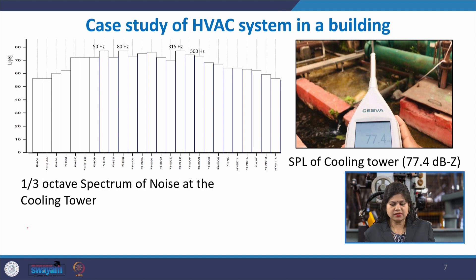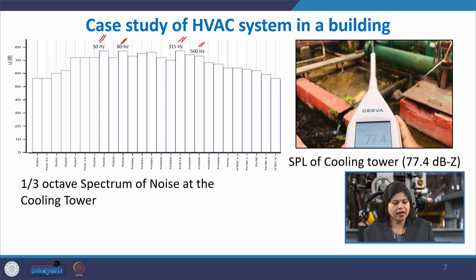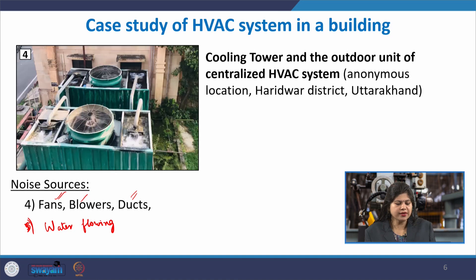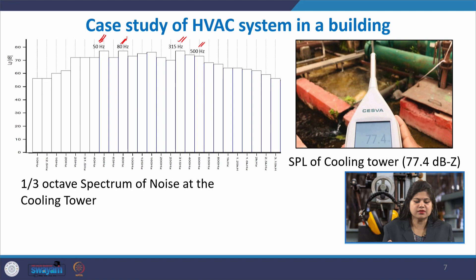We measured the noise level at the outdoor unit — it was around 77.4 dB Z — with octave spectrum peaks around 50 Hz, 80 Hz, 315 Hz, and 500 Hz. The outdoor unit has more fan noise; the noise is both structure-borne and airborne from fan noise and water flowing. The overall spectrum is more broadband with small, non-sharp peaks rather than sharp tonal peaks.